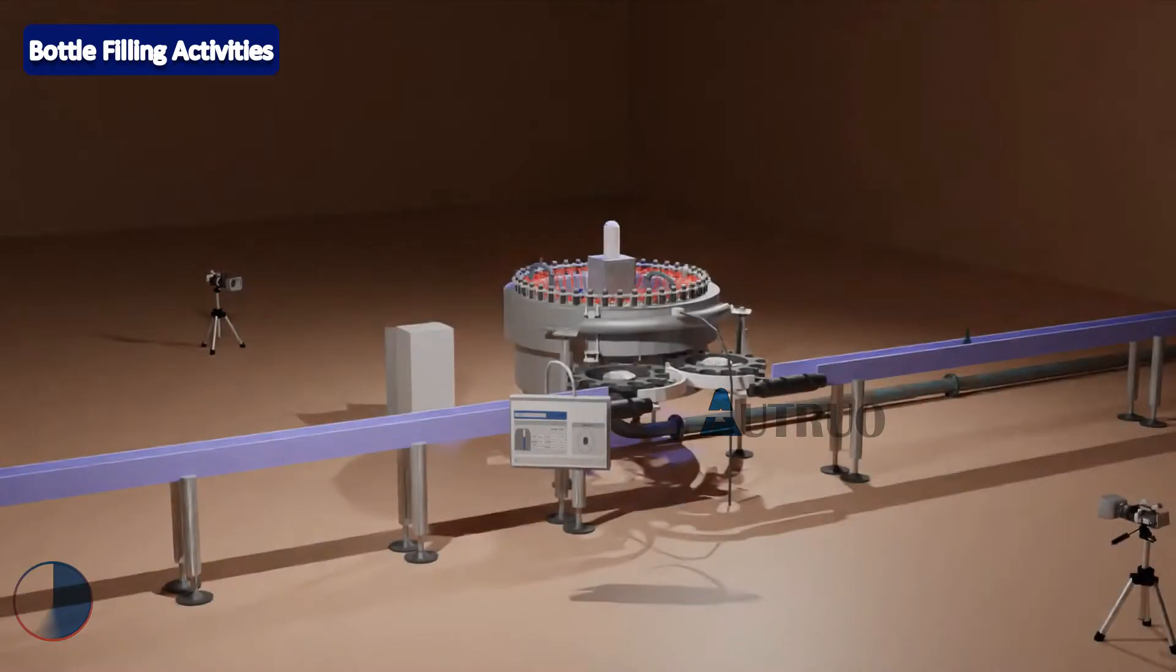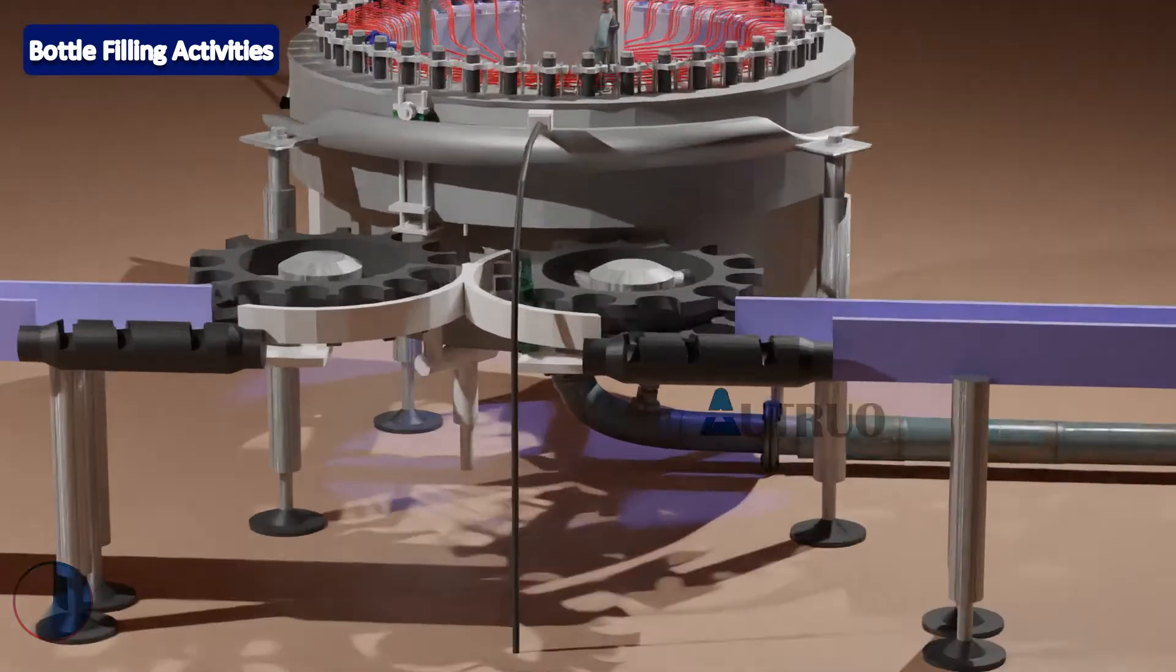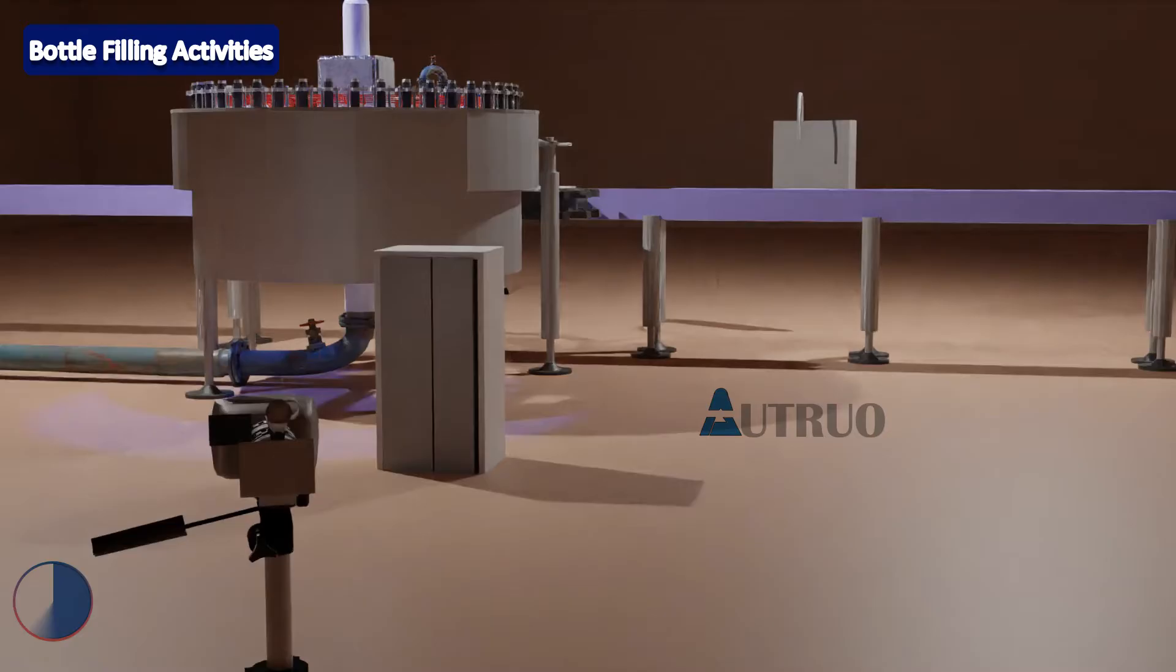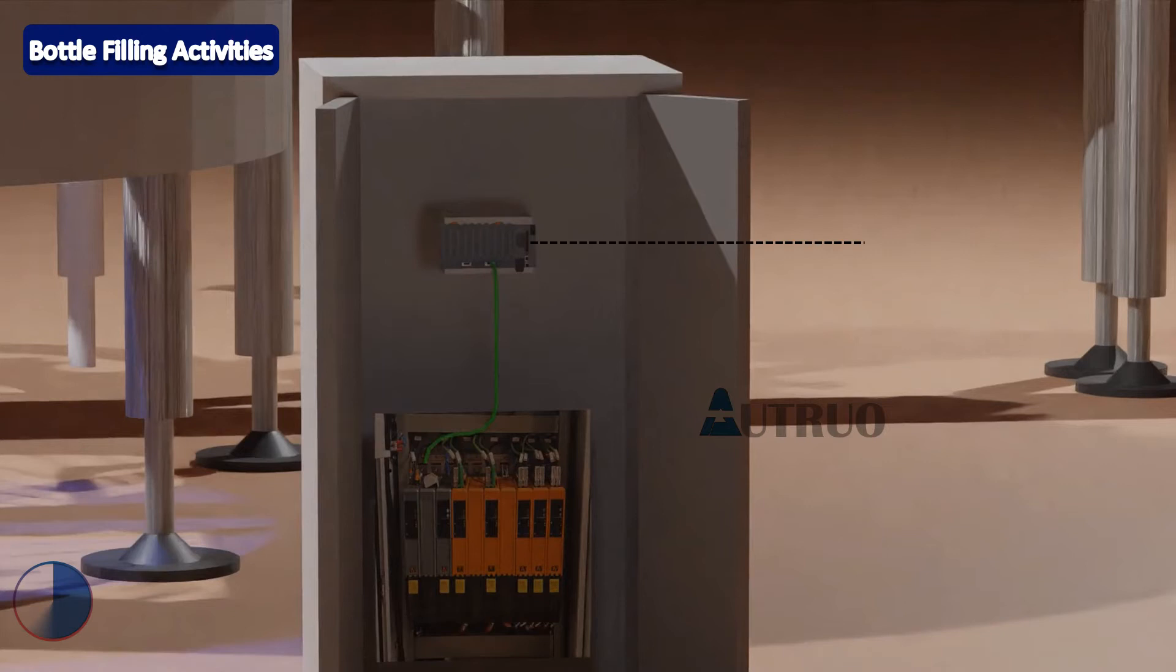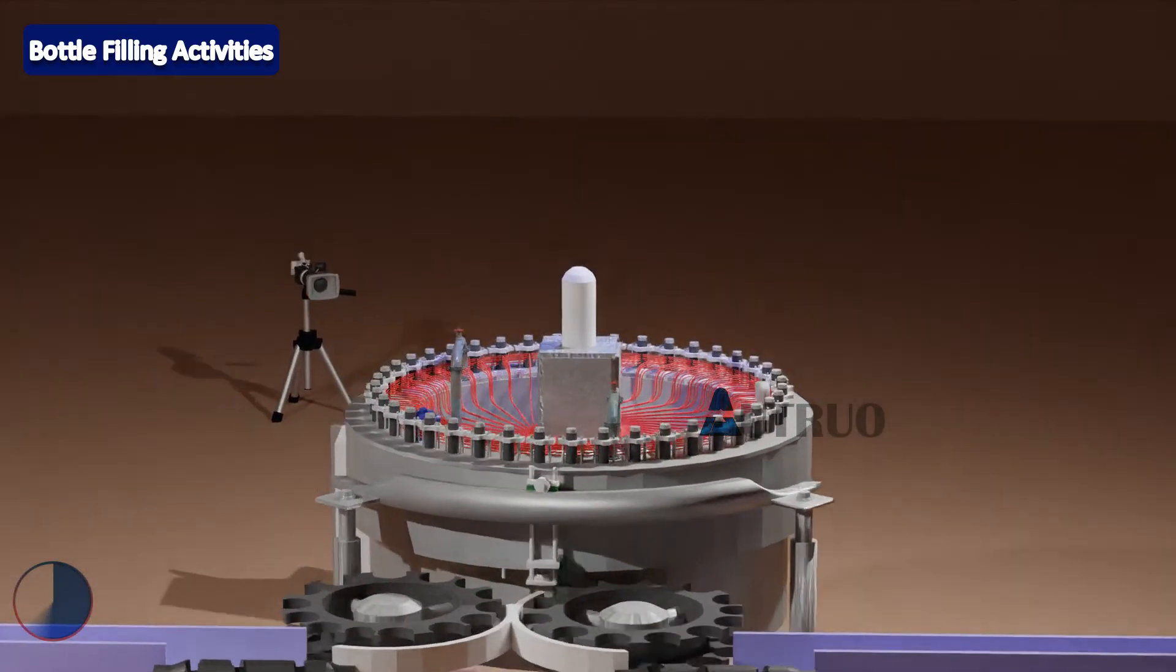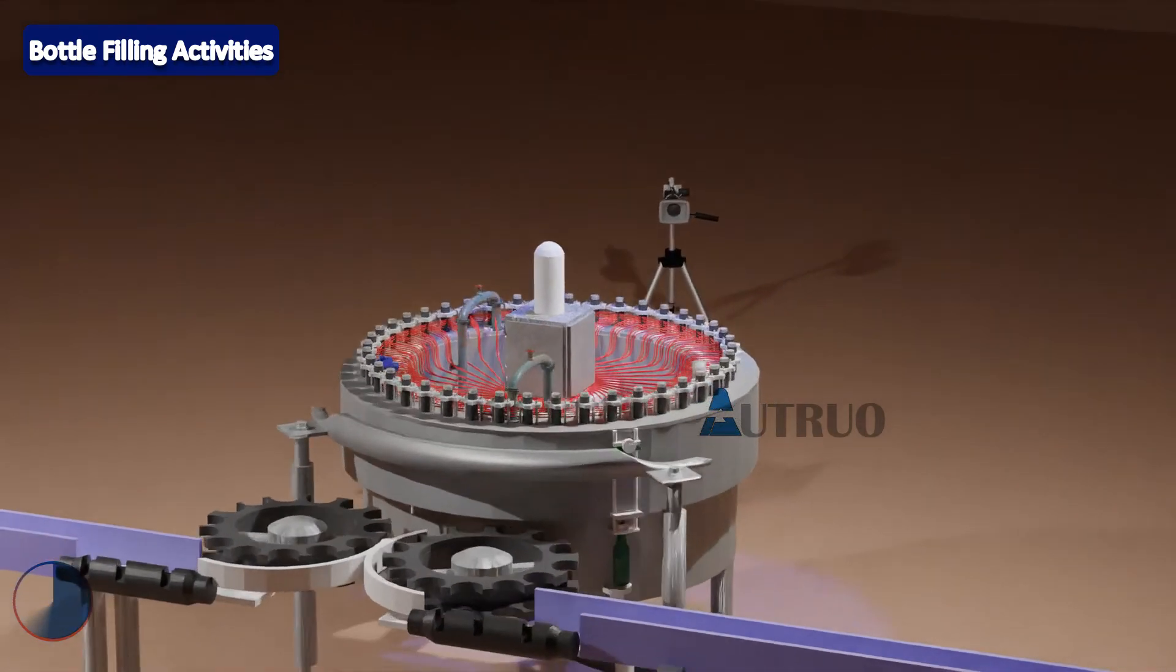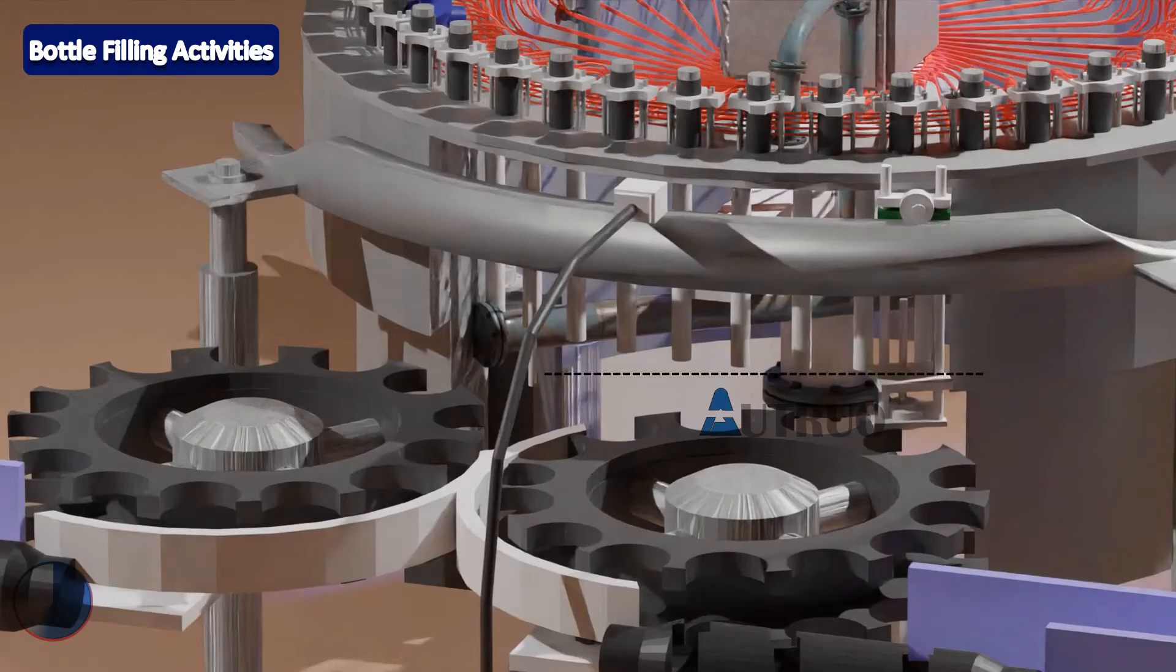Filling process is triggered by a sensor at the inlet of the filler. This sensor is known as bottle presence sensor. As soon as the sensor is triggered, the PLC, which is the B&R X20 CPU, will create a shift register. This register will be used to automate the filling of the bottle with beverage or alcohol as the bottle moves along its axis.